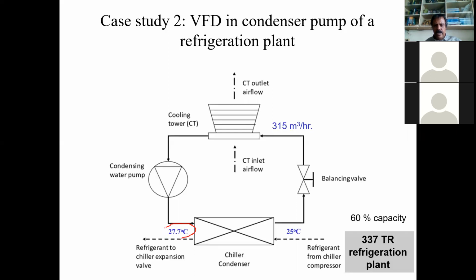So the difference again, the range of the cooling tower, is only 2.7 degrees, which means that the flow rate is very high. So the delta T is only 2.7 across the condenser, indicating high flow rates. In this case, it is designed for a range of 5 degrees. That means this delta T across the condenser is also the delta T across the cooling tower, which is the range of the cooling tower.